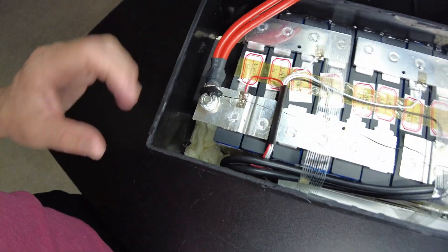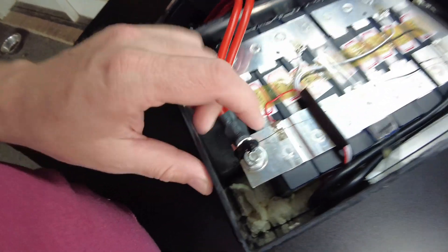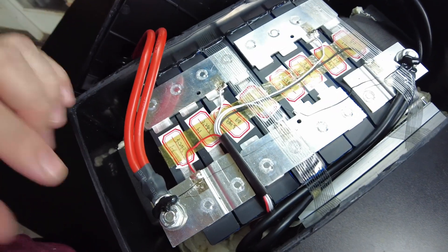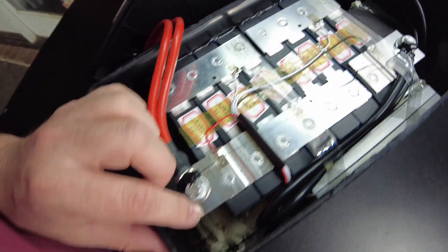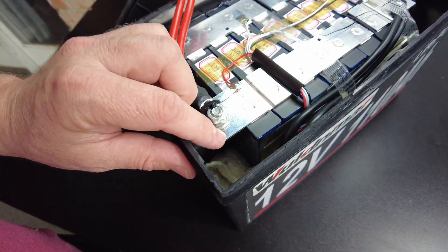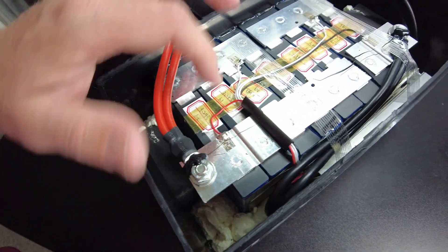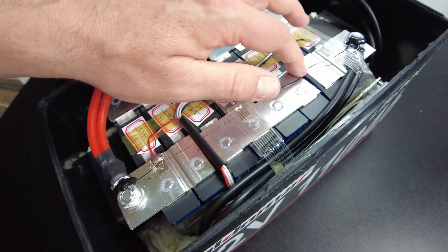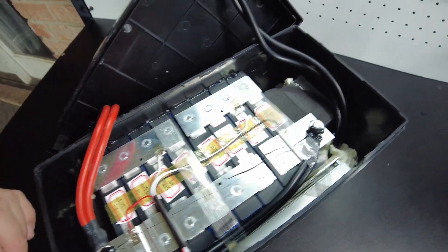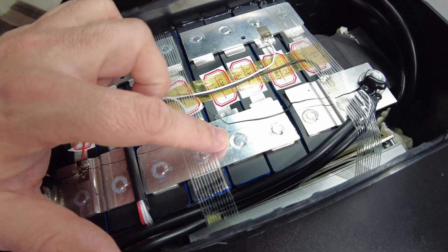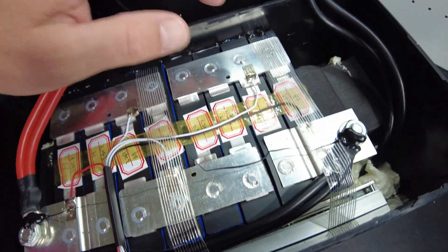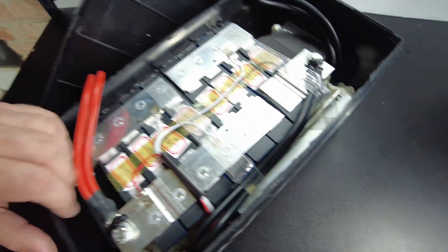It's got foam on the sides and then it's filled in with polyurethane foam. The construction looks fine. You know, aluminum bus bars, which is very typical these days, and they're fine. The aluminum bus bars are fine as long as they're thick enough, and it doesn't seem to be thin or anything like that.